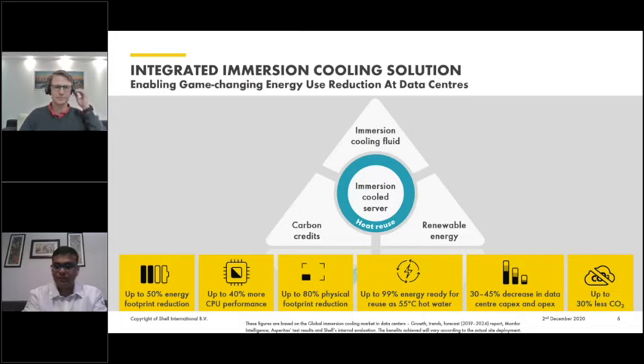Asperitas has done a lot of testing on this. Up to 50% energy footprint reduction is possible compared to an average data center, just by going for immersion cooling. You can also expect to increase CPU performance by up to 40%, because the electronic components are cooled so well that they can be clocked up to much higher speeds, giving much better performance.